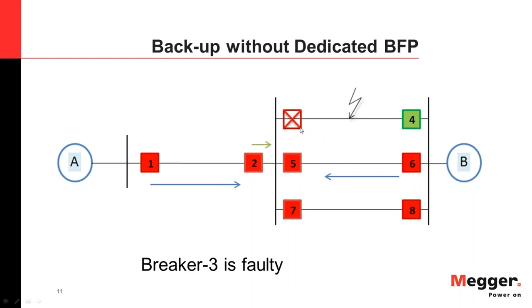Let's take an IEEE standard example — a two-source model with Sources A and B and a number of breakers, each assigned a number. Assume we have a fault between Breaker 3 and Breaker 4. With proper functioning of both breakers, Breaker 3 and Breaker 4 will open, there is no in-feed from the sources to the fault, and the fault is cleared.